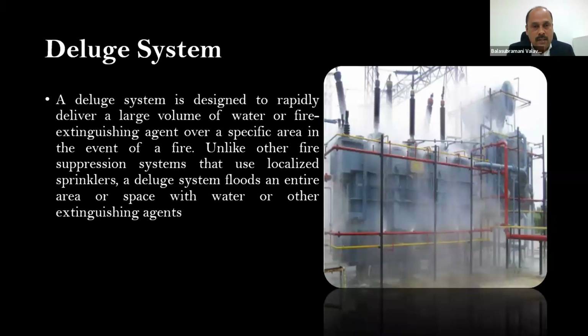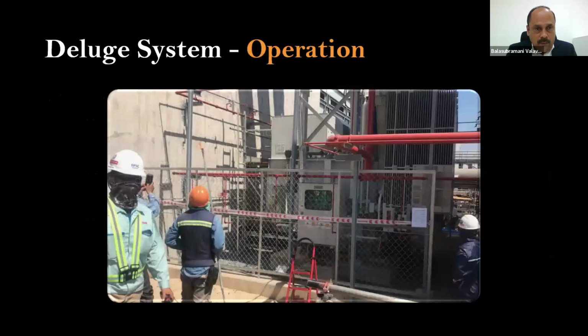Basically, the deluge system is used to put off the fire externally, nothing related to the internal of the transformer. It is to put off the external fire. The water will be flooded onto the complete area, which will put off the fire. How? We'll be seeing in the later part of the slides. Before that, I would like to show on video how the deluge system is operated. In this particular case, it will be operated manually.